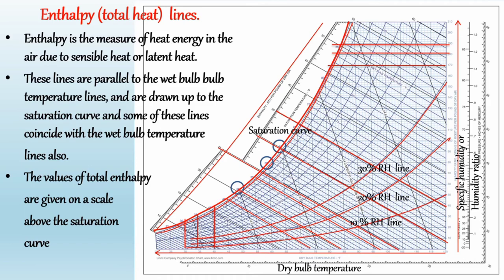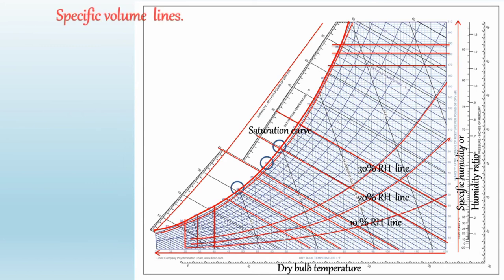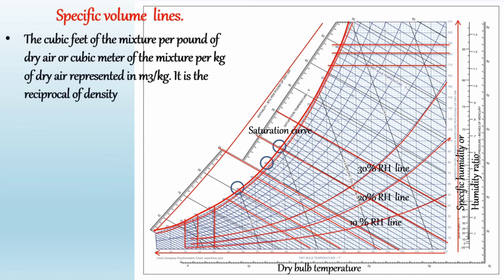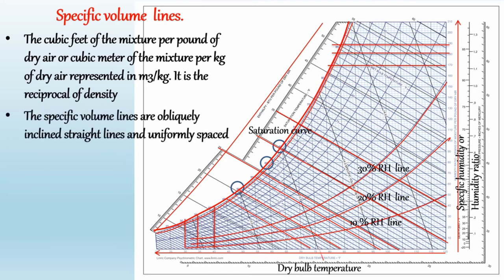The next line is the specific volume line. Specific volume represents cubic feet of the mixture per pound of dry air, or cubic meters of the mixture per kilogram of dry air, represented in meter cubed per kilogram. It is the reciprocal of density. In the psychrometric chart, the specific volume lines are obliquely inclined straight lines and uniformly spaced. These lines are drawn up to the saturation curve.